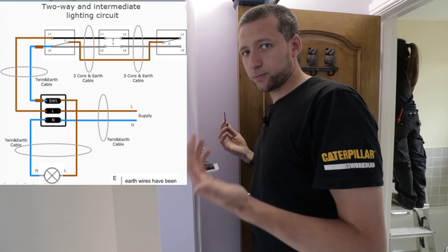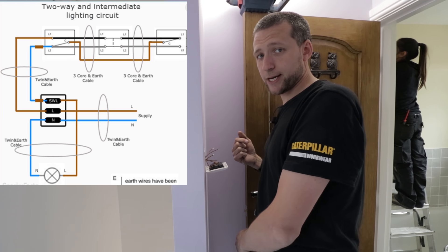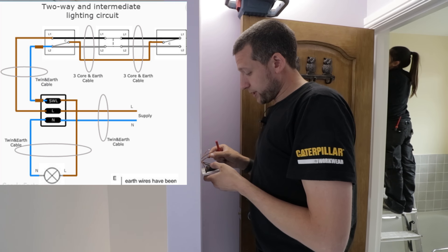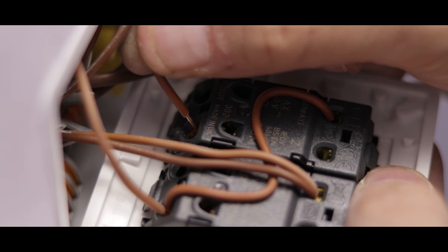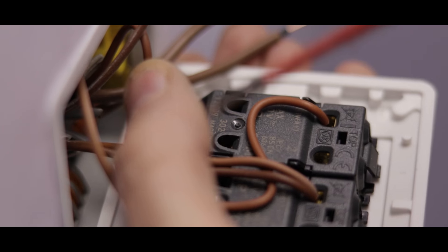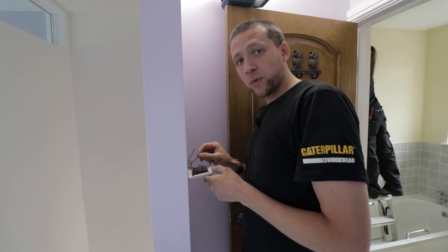So you've got your feed in which comes from your last light switch or wherever. You've got your three core and earth which goes down to the switch at the bottom of the stairs. Then you'll have your switch wire which goes up to your light fitting. Your brown of the three core — so you've got brown, black, grey — your brown always goes into the common on your switch. You should only ever have one wire in the common, except in the intermediate switch where you haven't got a common and all you'll do is bridge the wires together — but I'll show you that downstairs.